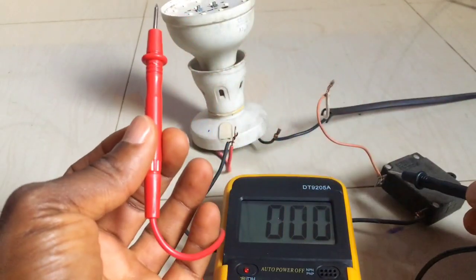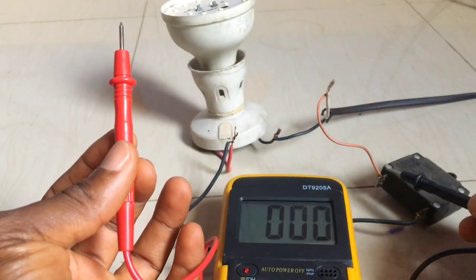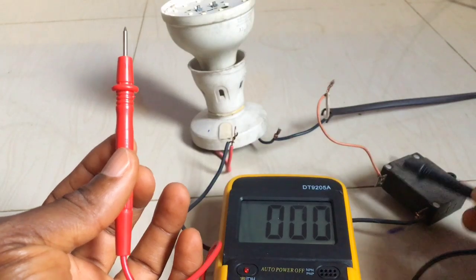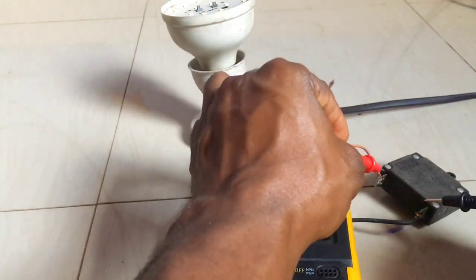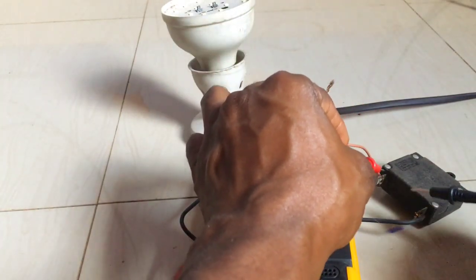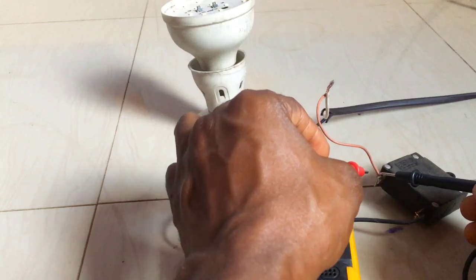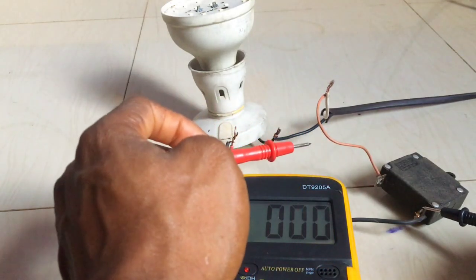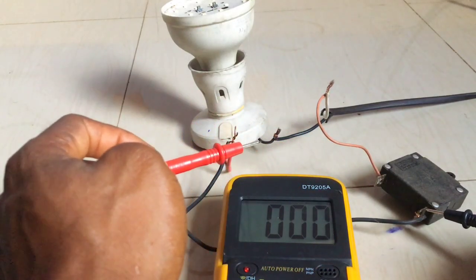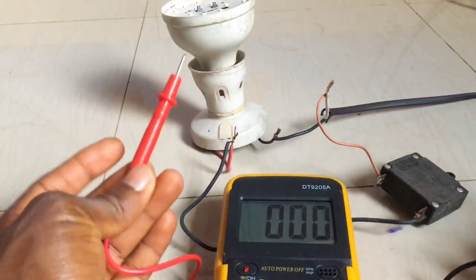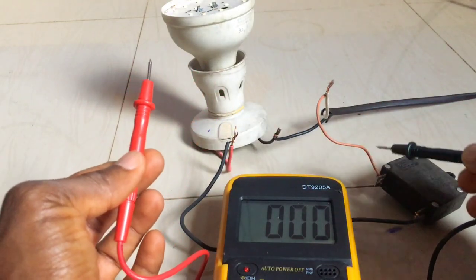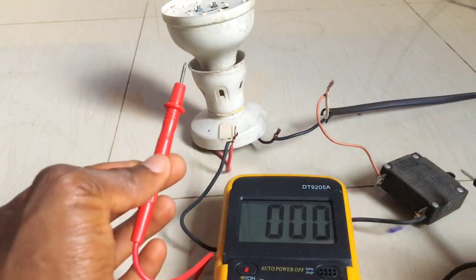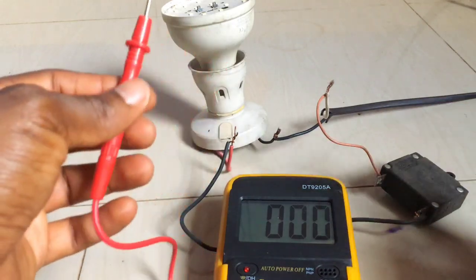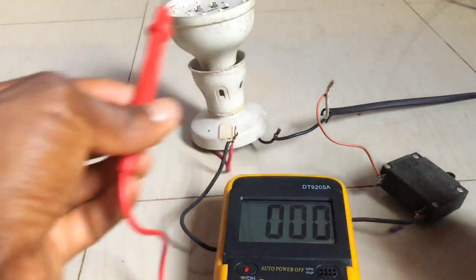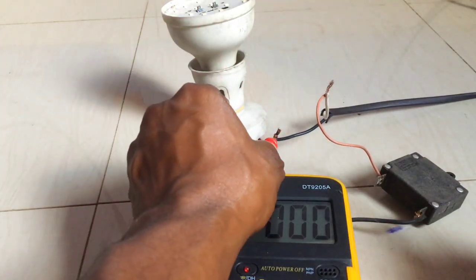It's either the common is not supplied. All right, so this is the common. How to check? If you test for voltage here, you're not going to get any voltage because this is just live from the common transferring to the branch going to your lighting point. So for you to know if the live wire coming from the distribution board or coming from another switch is energized, you have to pick neutral from anywhere. You can pick neutral from a socket, but this is our neutral link here.